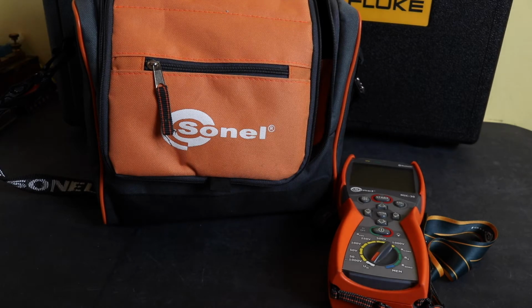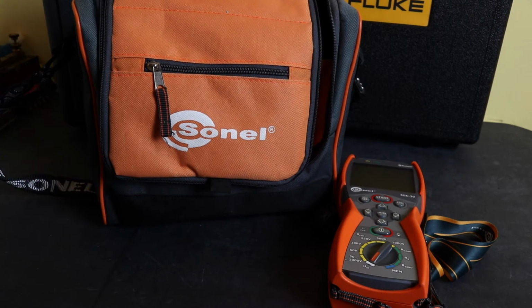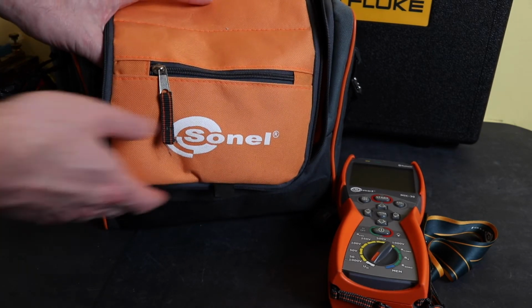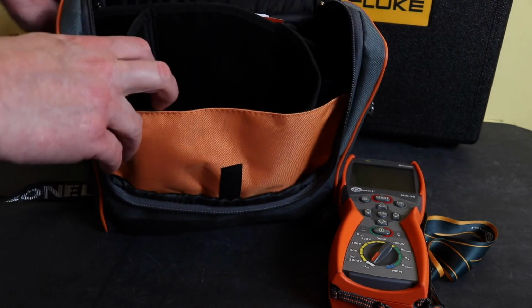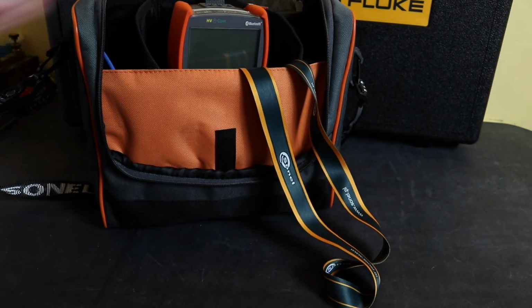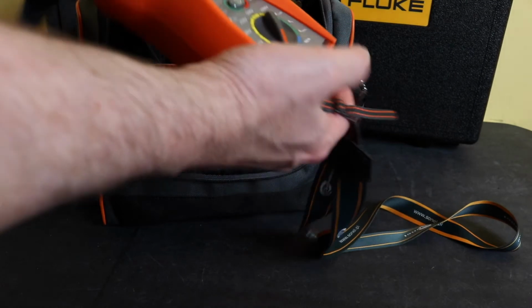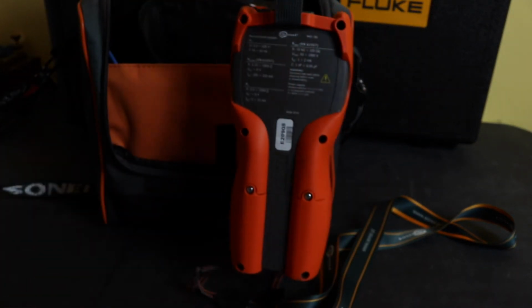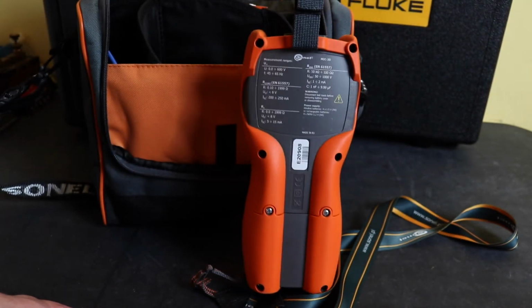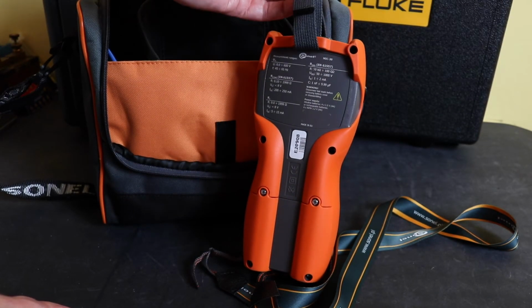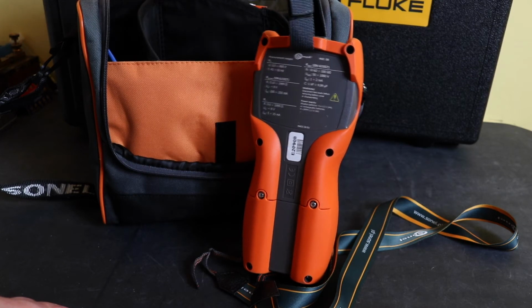And finally, the Sonel here, a completely different approach. You get this little soft case, a satchel kind of case, to house the instrument in. The instrument sits in the centre pocket in there. You do get a hanging strap to go with the instrument. You also get a strap to hang it from the top as well. It's not magnetic, it's a plastic hook to hang the instrument from wherever you can find, really.